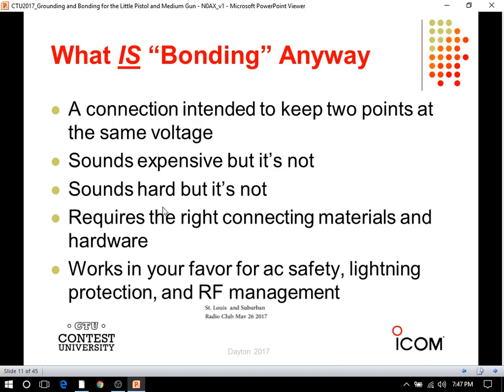The benefit you get from doing this bonding is it works in your favor for all three of those different needs: AC safety, lightning protection, and RF management. You don't have to create three different ground systems—an AC power ground system, a lightning protection ground system, and an RF ground system. Make them all one system. They'll work for all three purposes. You only have to do it once.